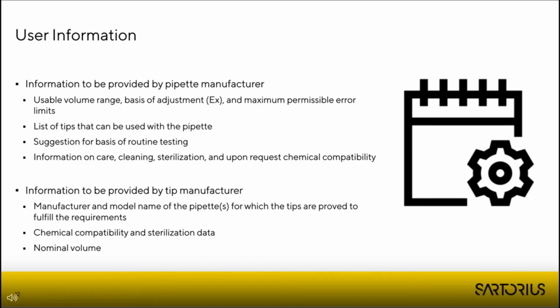Then the tip manufacturer, what information the tip manufacturer must provide. Per tip model, per tip type, the manufacturer must provide information on which manufacturer and which model of pipette the tips can be used with. This is something the standard series didn't touch earlier, because this is a brand new addition. Then chemical compatibility and sterilization data in case there are sterile tips. And then nominal volume. And here you see the difference: pipettes can have a volume range, but tips usually have a nominal volume only. Okay, that was about the tips.